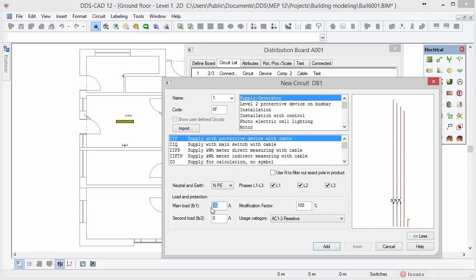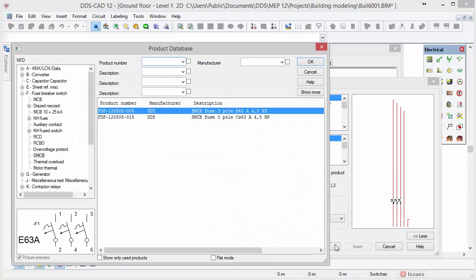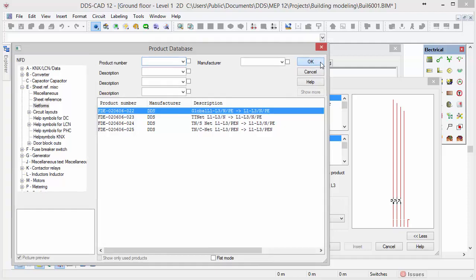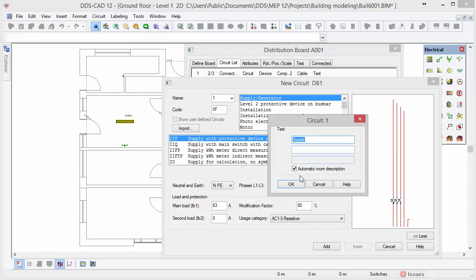We predefined the main load to 63 amperes and you can change the modification factor to 80%. Next click on the add button to open the product database for electrical components. Based on the settings we applied, DDS-CAD suggests an appropriate fuse. Select it and press OK. Here you can select the system configuration in relation to neutral and earth. Press OK to proceed. At last you can give a description to the circuit and click OK.